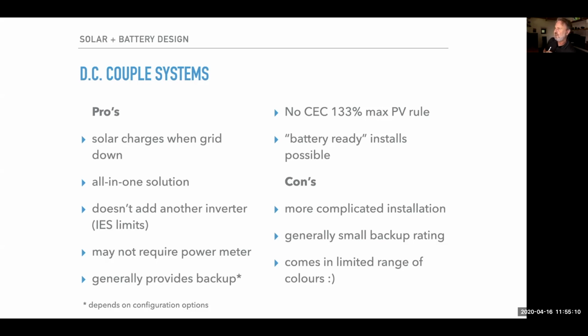So we've got a question here. I'm working with an Alpha 3-phase inverter, looking at putting in 3 2.9 kilowatt batteries, one on each phase. Great. I'm not sure if that's a question. It's a comment. So there is a requirement in our grid protection standard that once you get to 5 kilowatts on a multi-phase system, you need to have a balance across those phases. So you can't put more than 5 kVA per phase. So you need to have balance if you go over 5 kVA per phase. I guess that's kind of what Ella's pointing to.